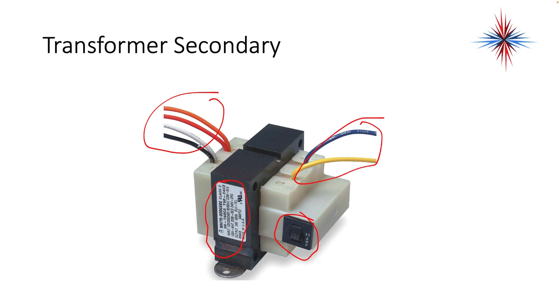In this case, we know that our black is going to be our common, white is going to be my 120, red is my 208, and orange is 240 — you can just see it in the label there. So it gives you an ability to use multiple voltages on a single unit, which is great to have in your service truck when you need to carry one part to serve multiple purposes.